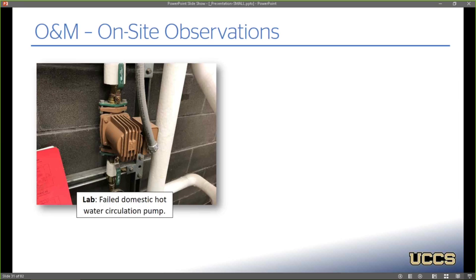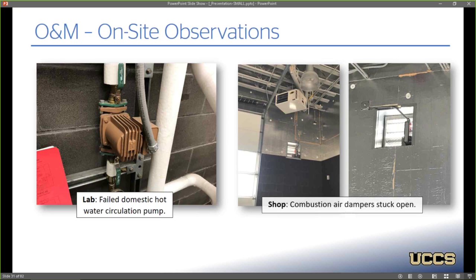The lab had an apparent failed domestic hot water circ pump. The owner didn't even realize they had a circ pump, but it was not operating, and they had a little wall switch that didn't appear to do anything.